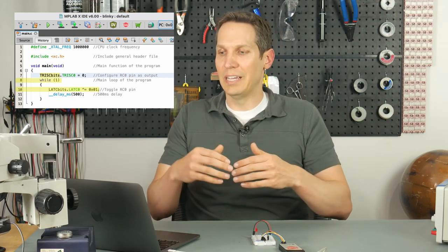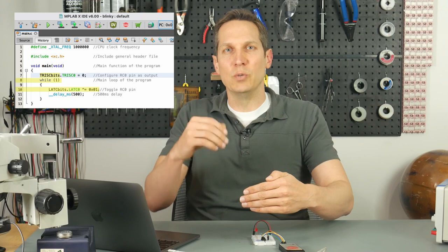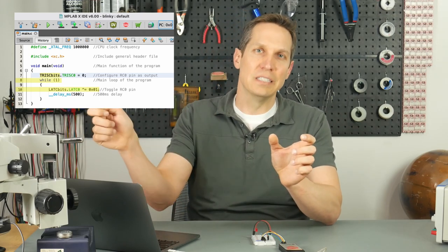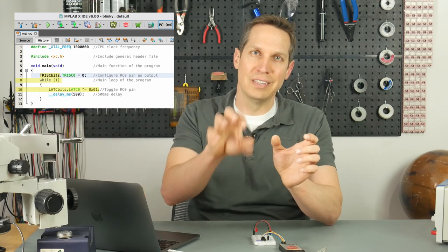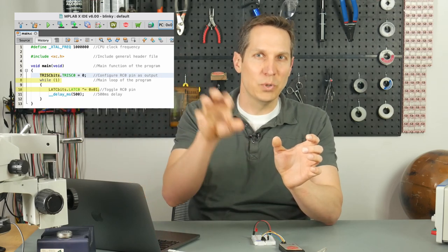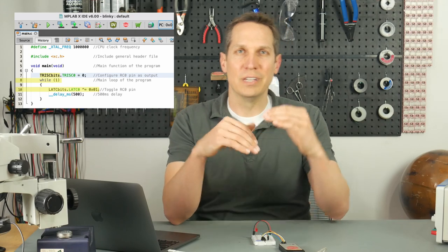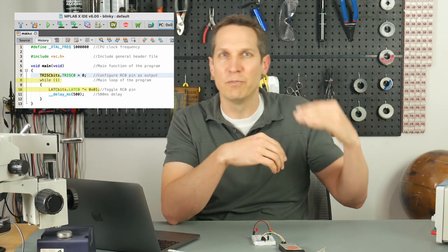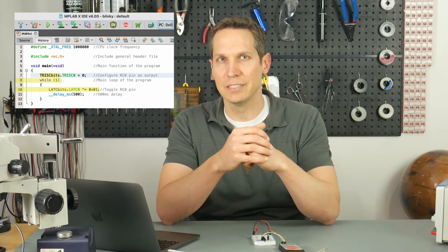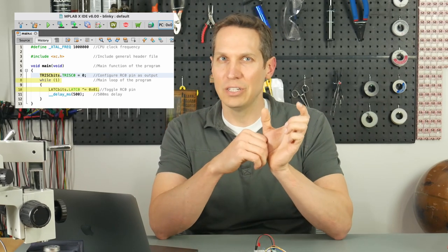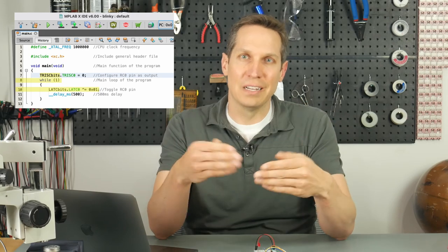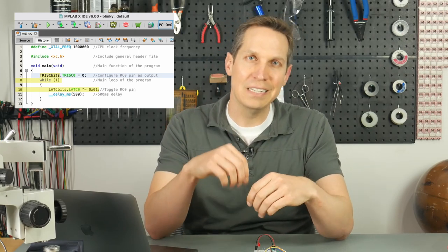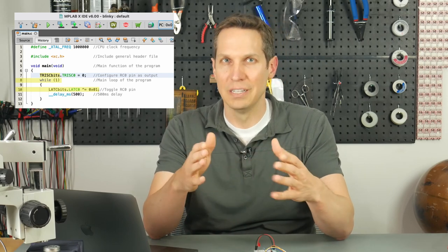It comes up where you'll say, hey, I want this bit to be 1. And so you use your lat command, say, set this to 1, and then you immediately tell something else to use that state, but it's pulling off of the actual voltage level, and it takes some time to ramp up, or it runs some other commands before it gets to that, or something along those lines. And so with your latch, just know that that's you saying, I want it to be high or low. But if you ever want to see what the actual real state is right now, that's where you use port.